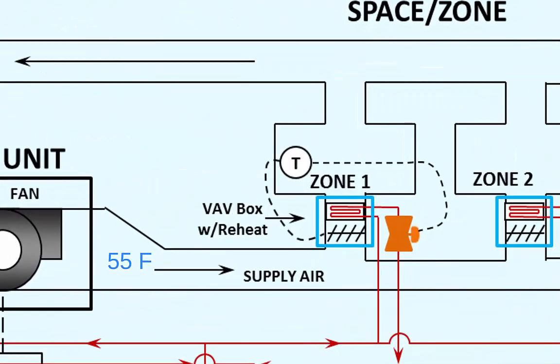Only now, the VAV box has two control devices in it, the damper and the hot water control valve. How exactly the controller controls these two devices is often a point of confusion, so let's try to clarify that here. One quick note, I'm going to present a control sequence here that is by far the most prevalent one used in controlling VAV boxes. There are some other approaches, however, but we can save that for a discussion on the LMS.